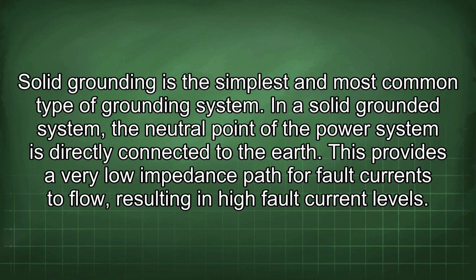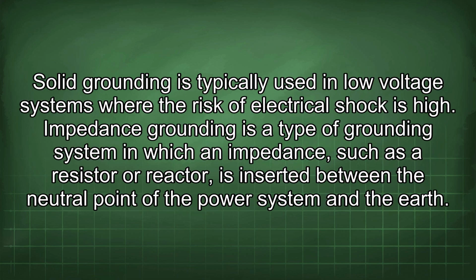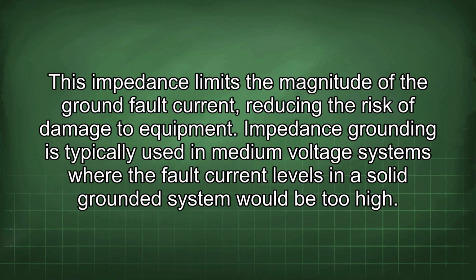In a solid grounded system, the neutral point of the power system is directly connected to the earth. This provides a very low impedance path for fault currents to flow, resulting in high fault current levels. Solid grounding is typically used in low voltage systems where the risk of electrical shock is high. Impedance grounding is a type of grounding system in which an impedance, such as a resistor or reactor, is inserted between the neutral point of the power system and the earth. This impedance limits the magnitude of the ground fault current, reducing the risk of damage to equipment. Impedance grounding is typically used in medium voltage systems where the fault current levels in a solid grounded system would be too high.